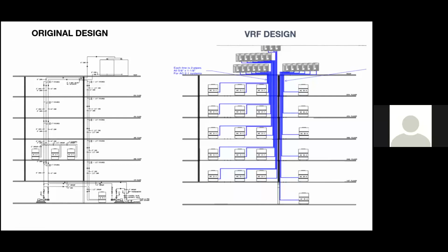And then these pipes are around 1 inch in diameter, which I'll actually touch on the next slide. So pretty small shaft space is required to fit all these. I think it was around 8 inches by 2 feet, the shaft space we used to fit all the pipes. I actually show a visual of this as well in the next few slides. So really pretty simple. And with this VRF design, we didn't need those additional components like the boiler, pumps, and cooling tower, like that water source heat pump design.